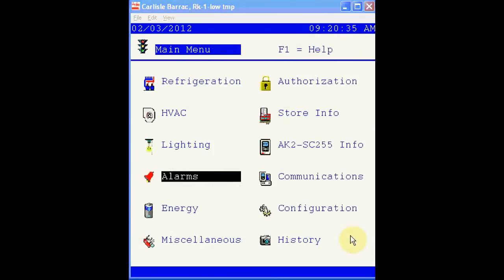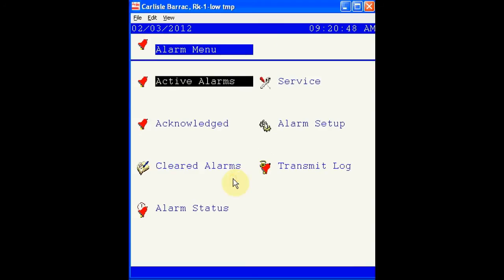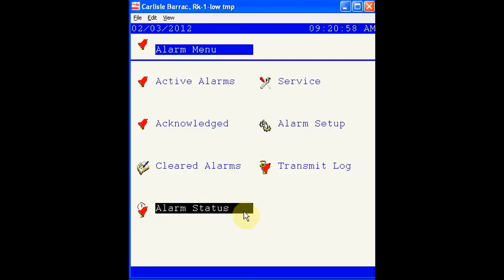From the main menu, we can find information about alarms that may have occurred in the past and alarms that may be in pending mode before you leave the store. Let's take a look at the alarms menu seen from the main menu. Here we have the option to view active alarms, acknowledged alarms, and cleared alarms. It's important to note that the alarm status is used by many mechanics and technicians to view the status of alarms that may be pending before they leave the site.